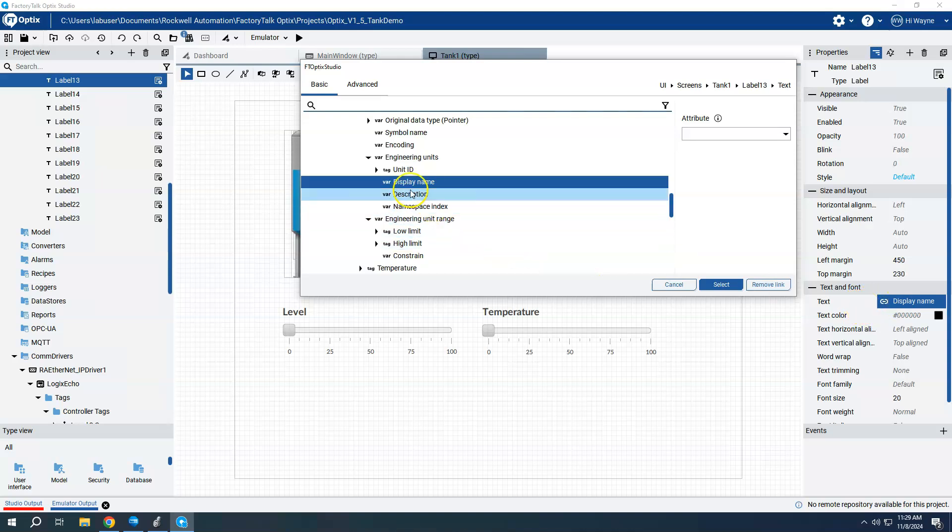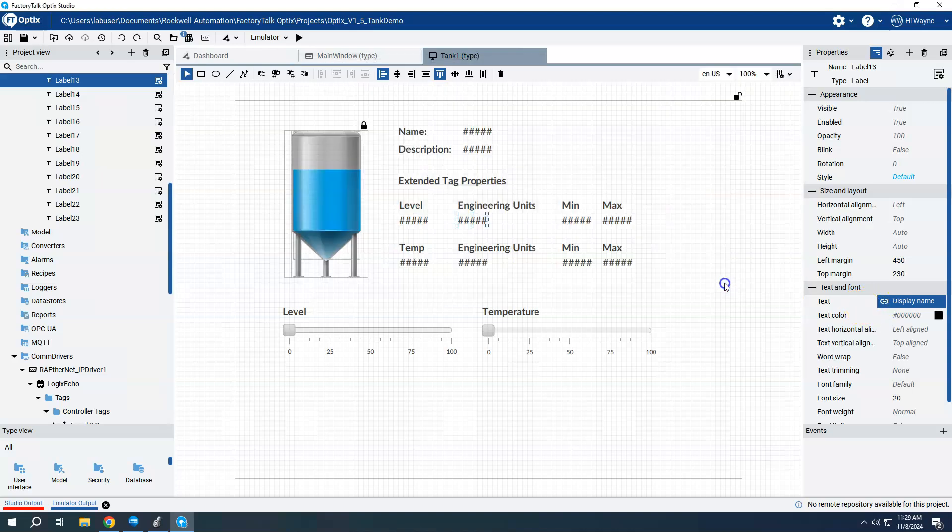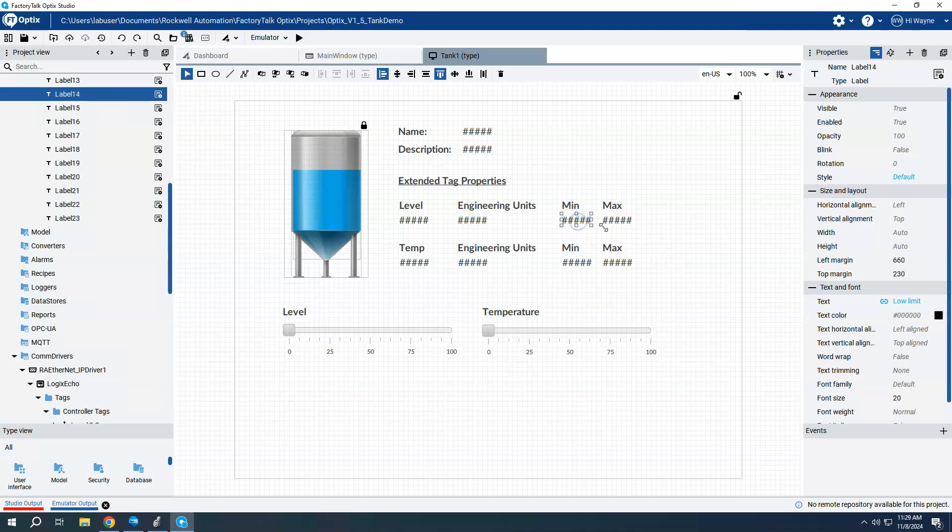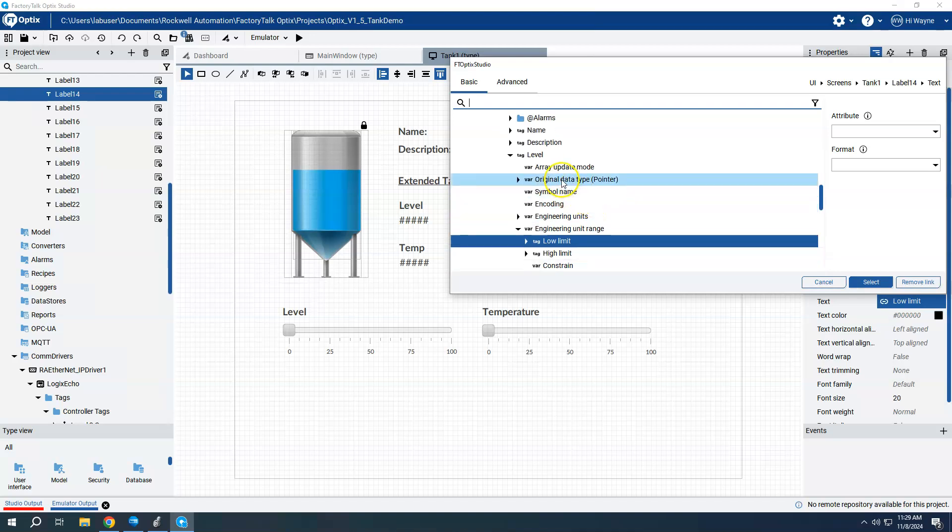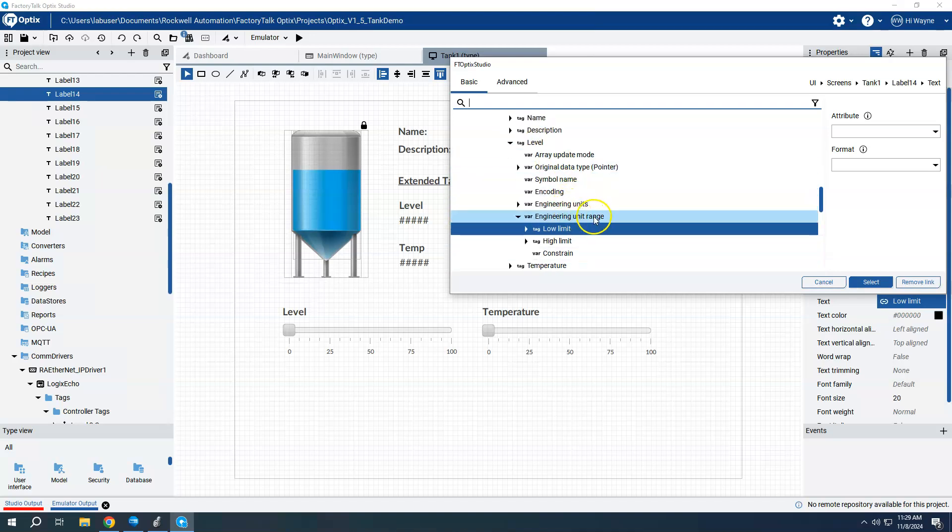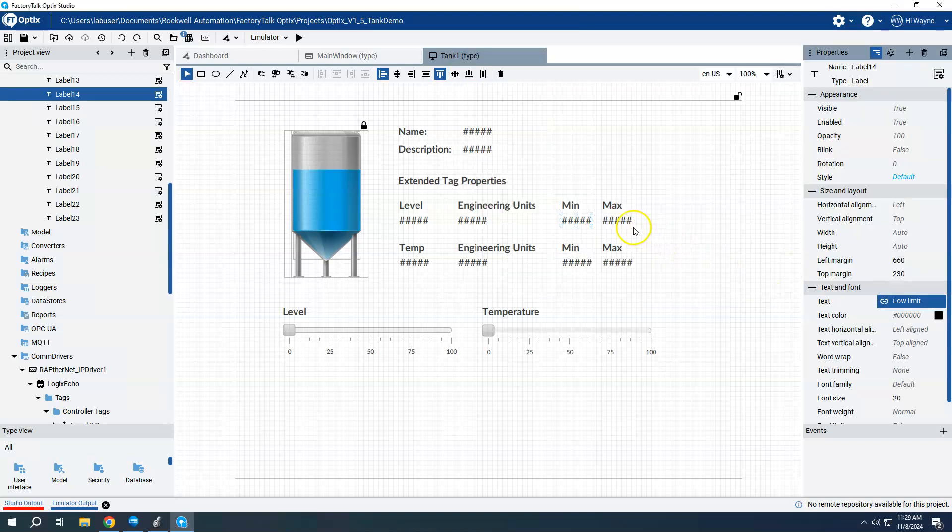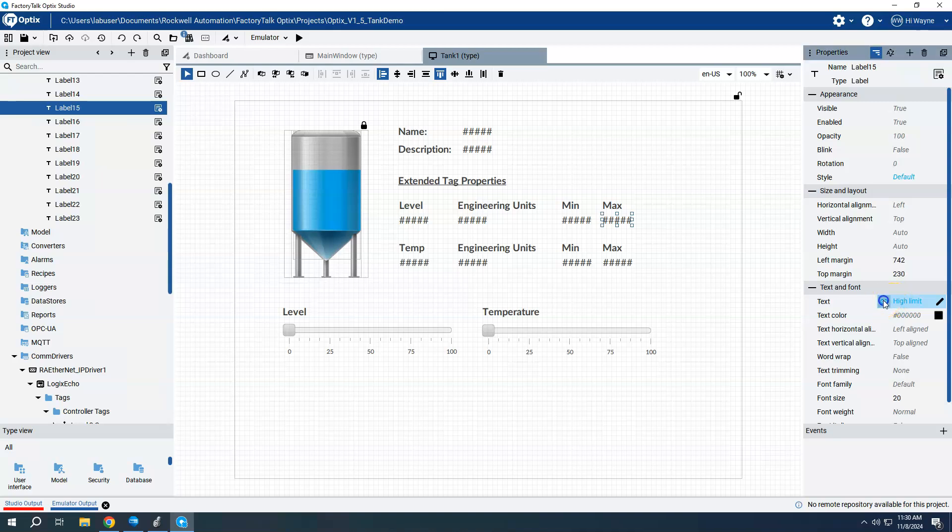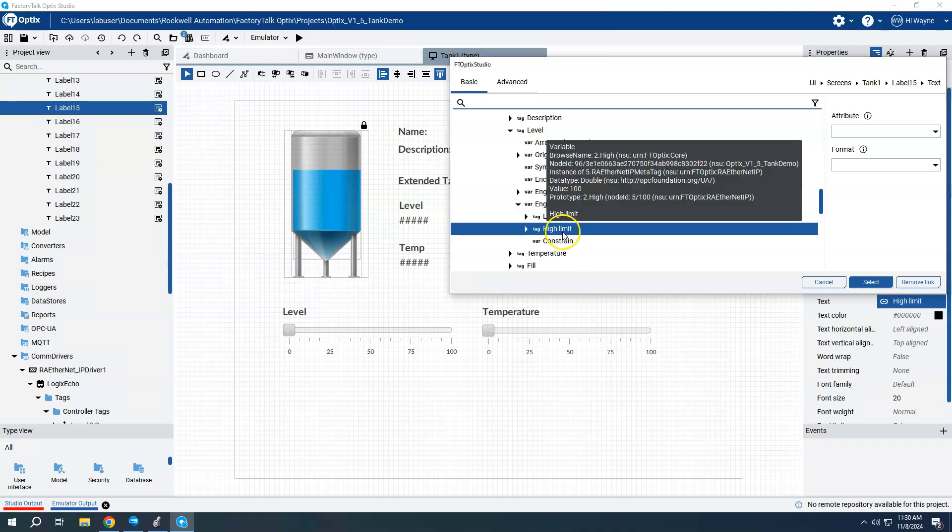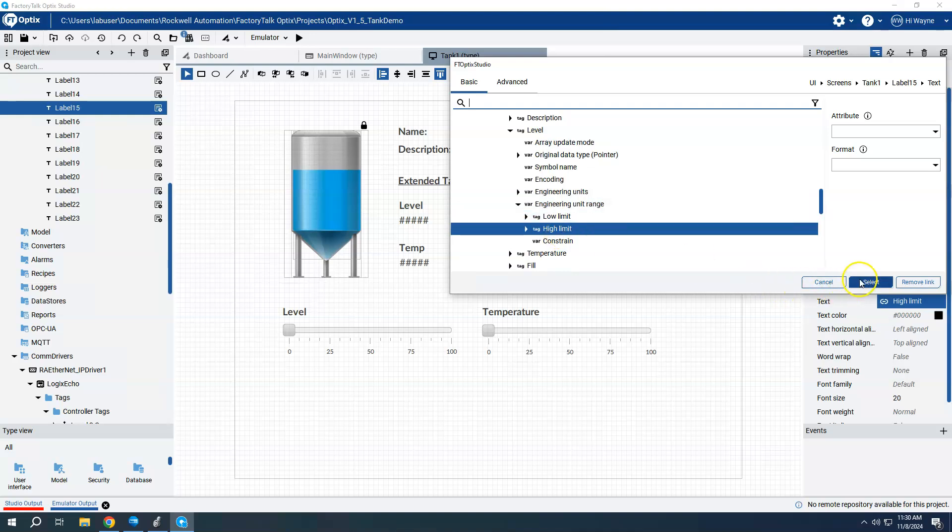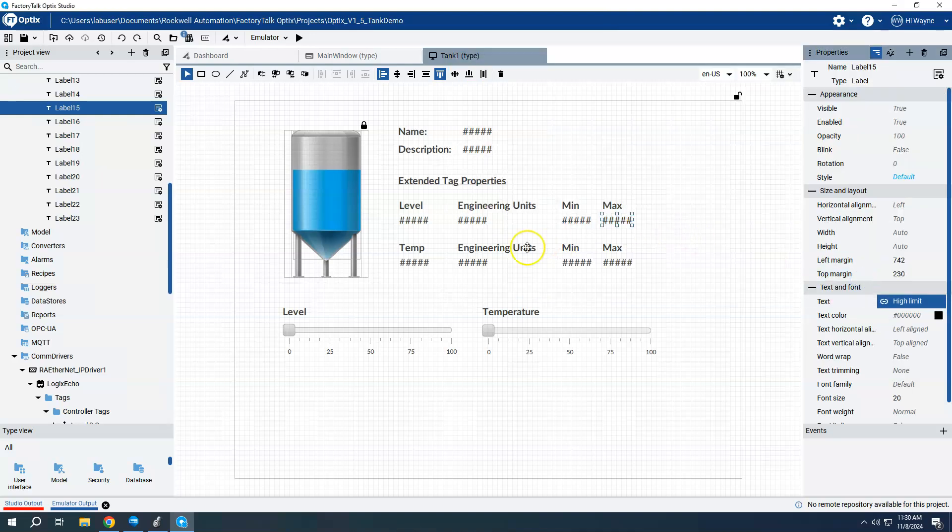So for this first one, I want the engineering unit display name, just like it is. And then for my min and max, if I come here to my minimum, this is my level engineering unit low limit. And then my max, of course, is going to be my level engineering unit range high limit. And now I did the exact same thing for temperature, engineering units here, min and max as well.